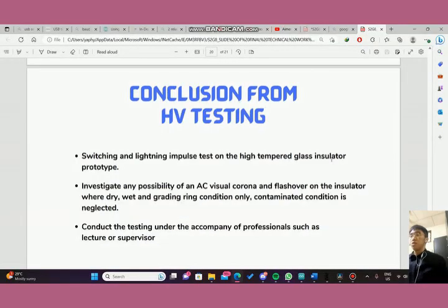Okay, in conclusion, high voltage testing can be carried out as proposed, via the method of switching and lightning impulse tests on the high tempered glass insulator prototype. A voltage of 275 kV or higher is planned to be applied on the insulator prototype to test the insulator flashover and withstanding ability under different conditions, which are dry, wet, and grading ring condition. The contaminated condition is neglected as it is too difficult to imitate or achieve real situations, and it would be tough to collect genuine data.